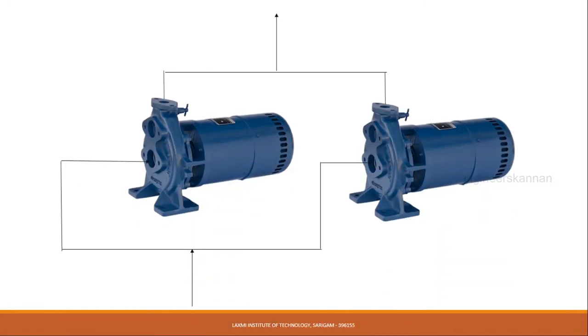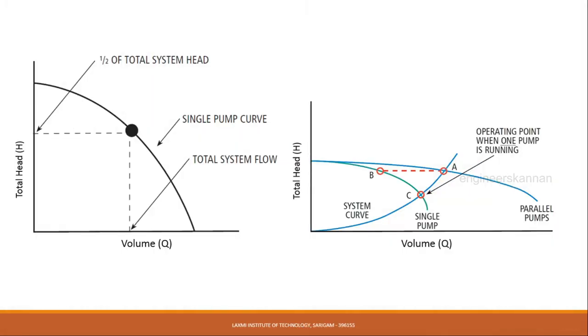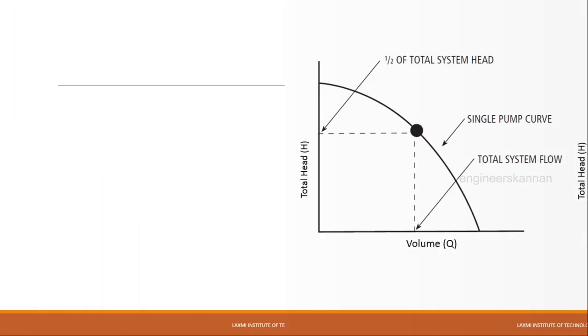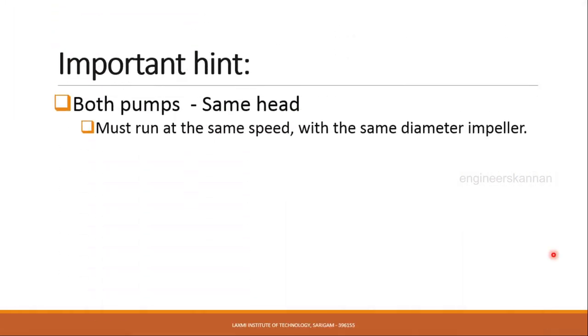Next we discuss parallel operating performance of pumps. The image represents two pumps connected in parallel. This configuration is used to increase the volume of water or fluid delivered by the pump. The performance curve indicates when a single pump is used versus when two pumps operate in parallel. The major thing is the total head is not changed, only the volume delivered is changed.